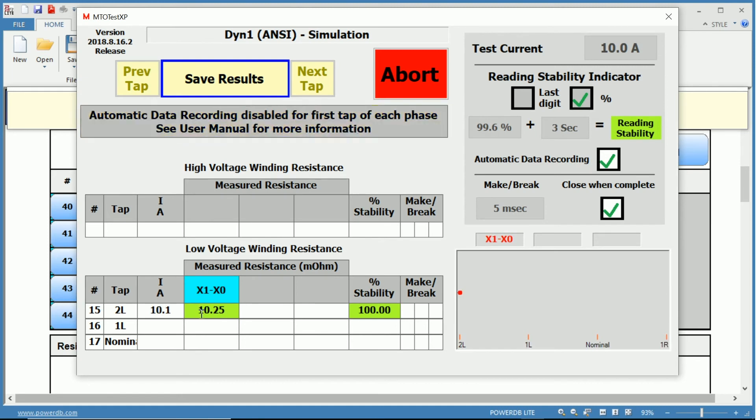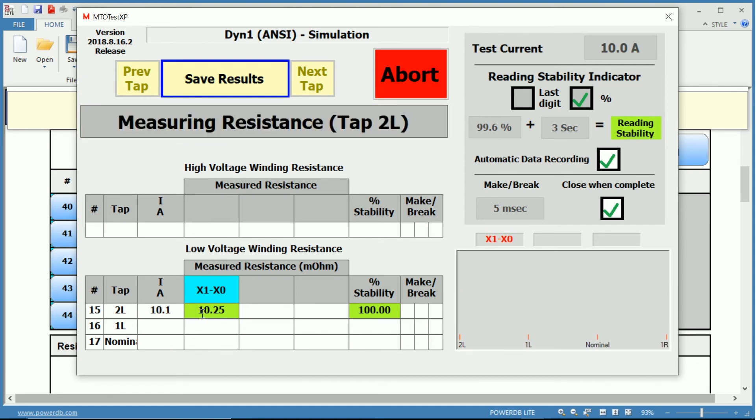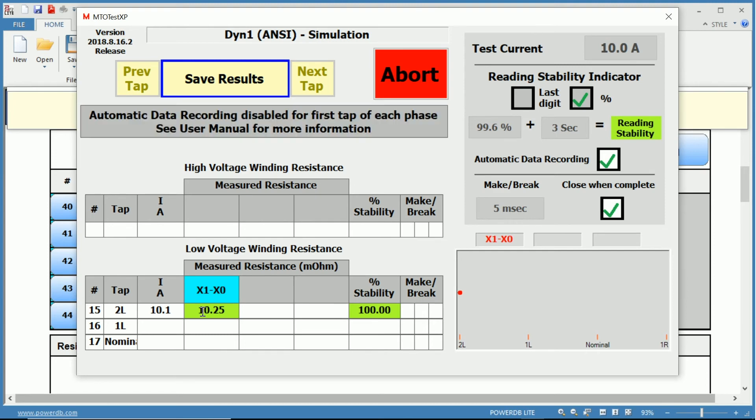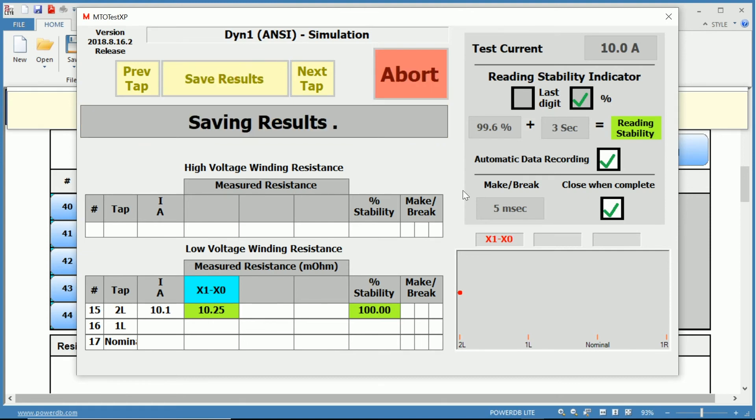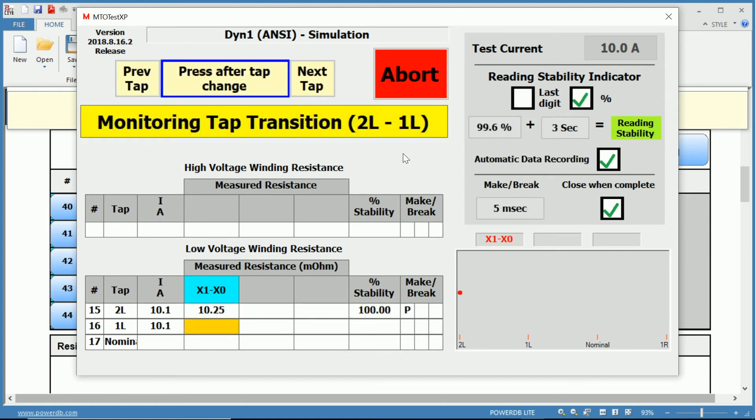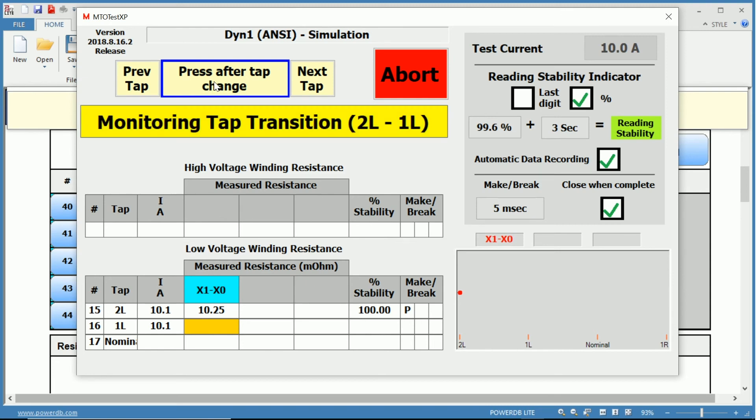Now we're measuring the resistance. We have our measurement. Our stability was 100 percent. The test current was 10.1 amps, and the measured resistance was 10.25 milliohms. Now that we're satisfied with that, we can save. Again, first result, and then it will start to do the automatic saving after.